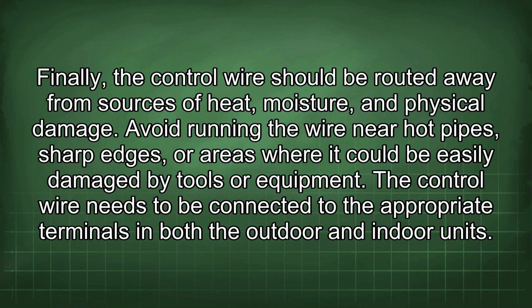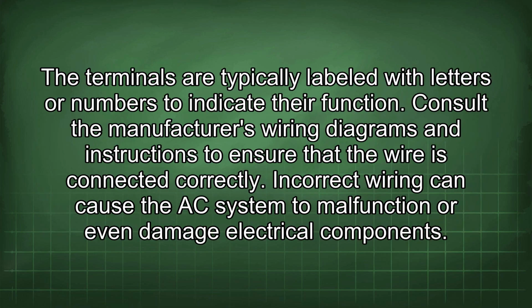Avoid running the wire near hot pipes, sharp edges, or areas where it could be easily damaged by tools or equipment. The control wire needs to be connected to the appropriate terminals in both the outdoor and indoor units. The terminals are typically labeled with letters or numbers to indicate their function. Consult the manufacturer's wiring diagrams and instructions to ensure that the wire is connected correctly. Incorrect wiring can cause the AC system to malfunction or even damage electrical components.